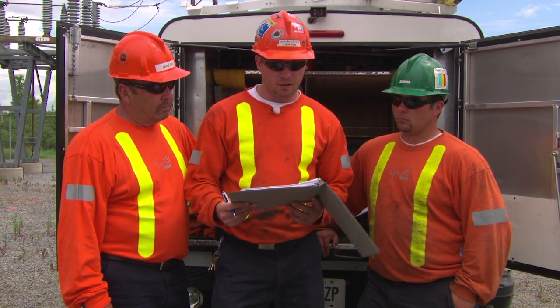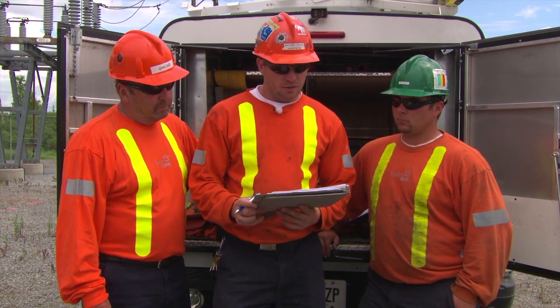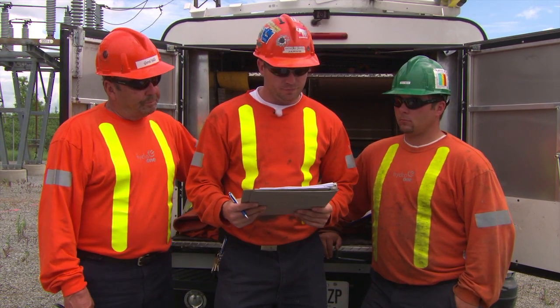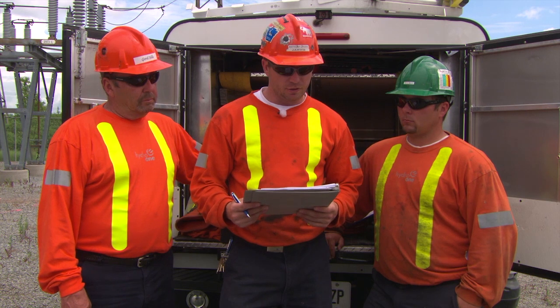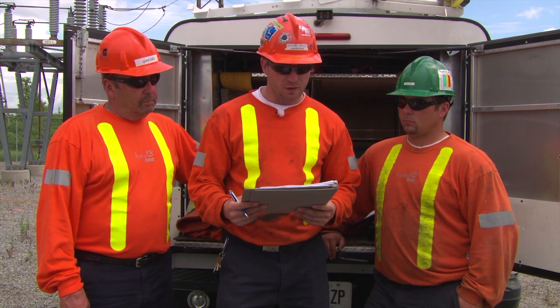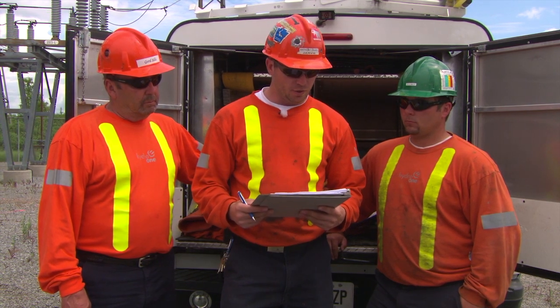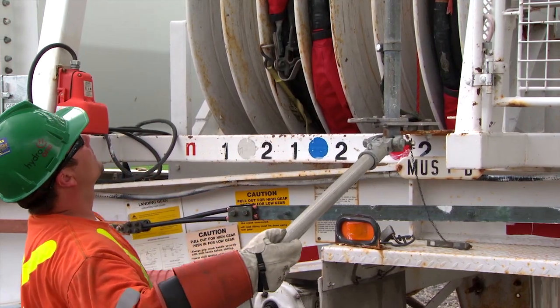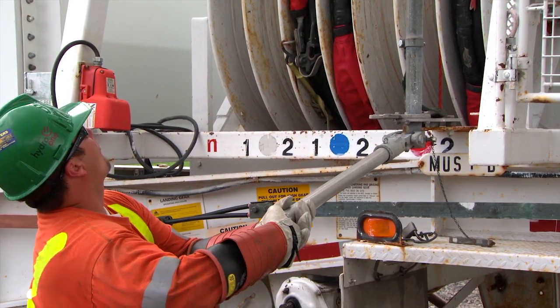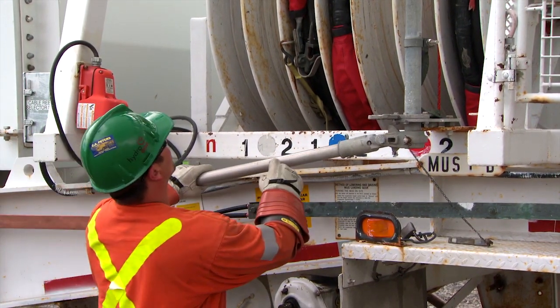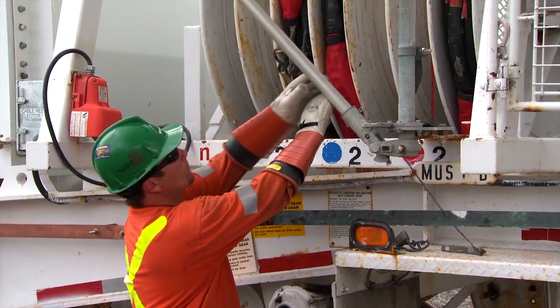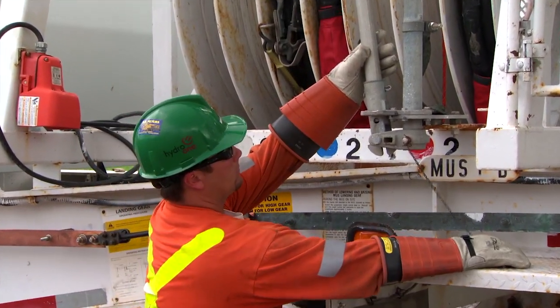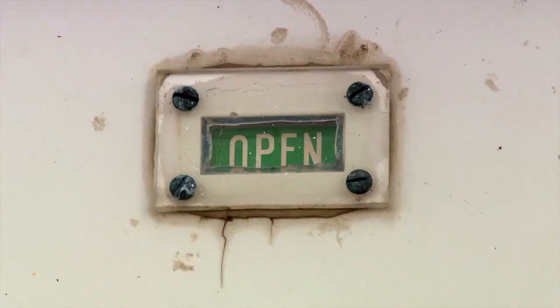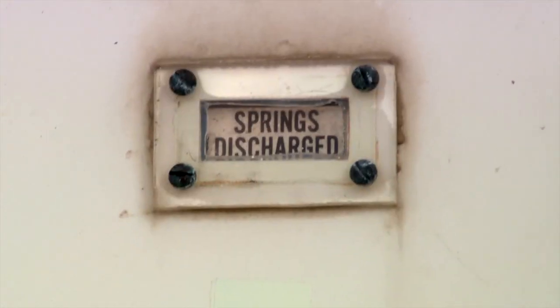After the reclosers have been verified, it's time to connect the low-voltage cables. Establish a self-administered work permit that allows you to safely connect the low-voltage cables. Open the MUS T-B low-voltage switch. Check Open, Locked, and Tagged. Check that the F1 OCR is open with the springs discharged.